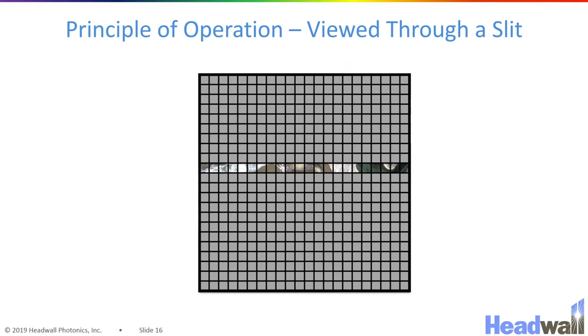Headwall's imaging spectrometers are push-broom imaging spectrometers that take an image of one sliver of the scene at a time. The image of the scene is projected onto a slit that cuts off all except for this one sliver of the scene for every frame gathered on the focal plane array, and therefore requires movement of some kind to collect the other spatial dimension.